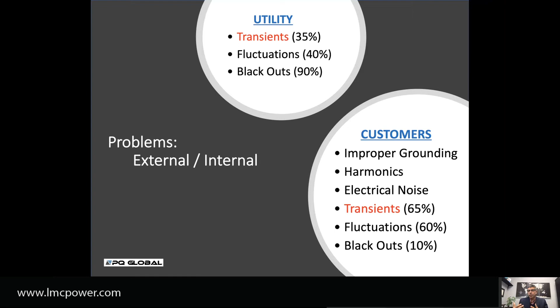Where there's a lot of misconception is on the inside of the building. People don't realize their own equipment is creating transients. So 65% of the problems are these—they're not dependent on atmospheric issues, they're dependent on your own facility. Lamarche has manufacturing equipment and everything, and we've already protected that against surge.